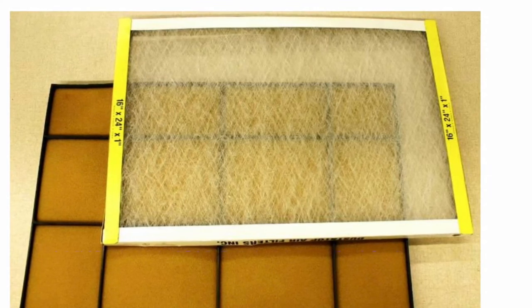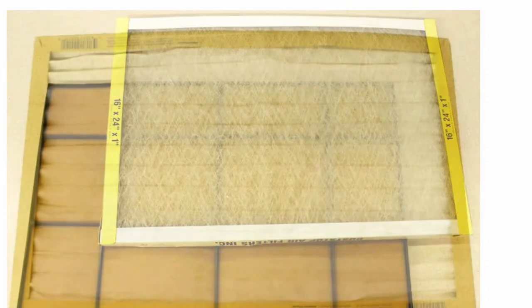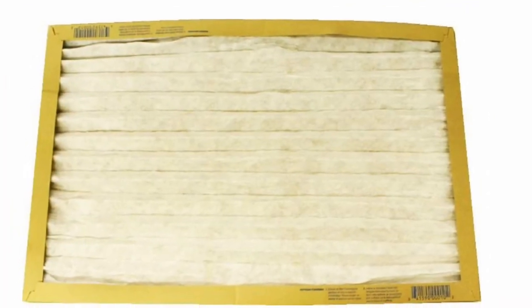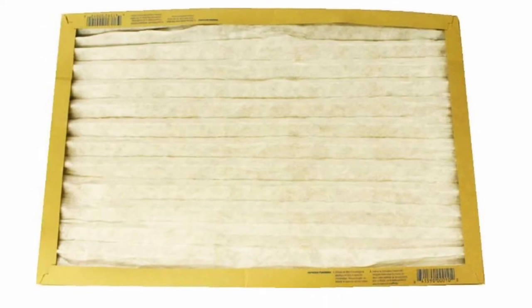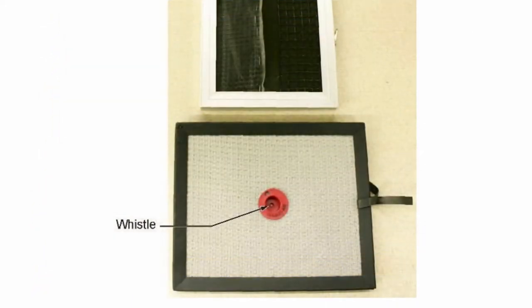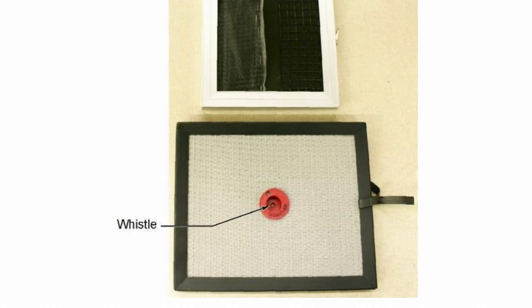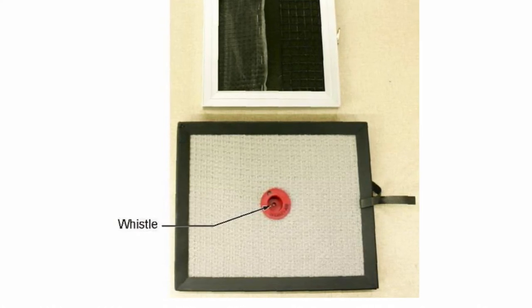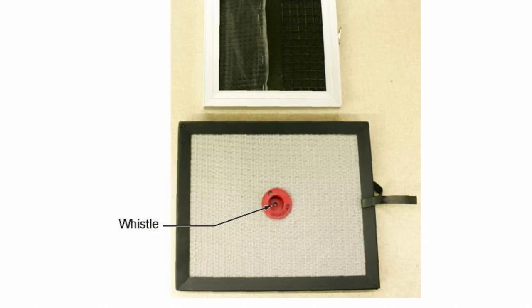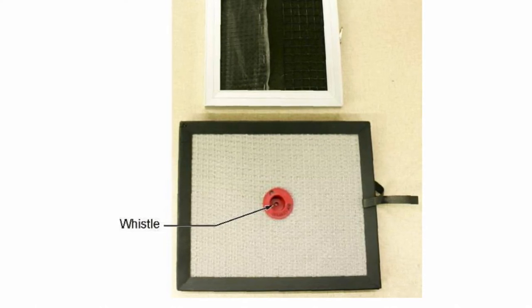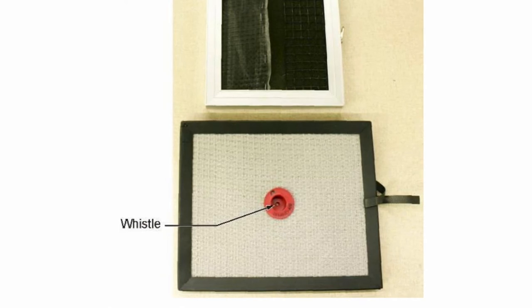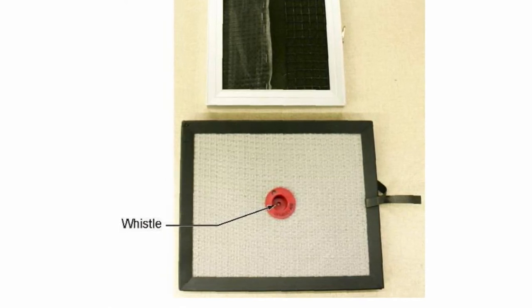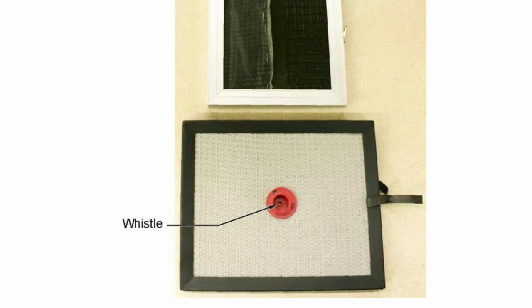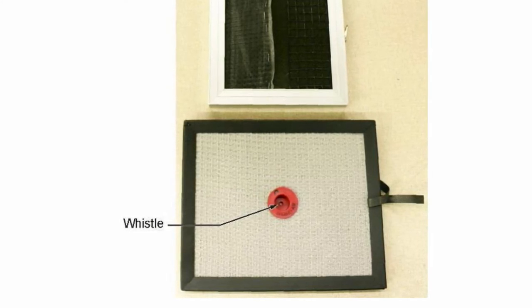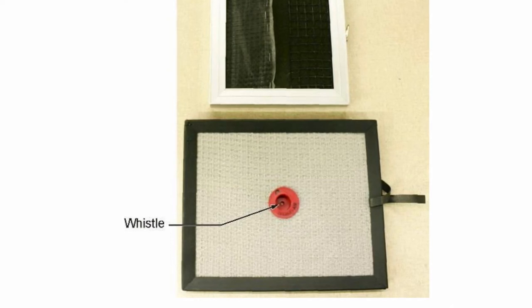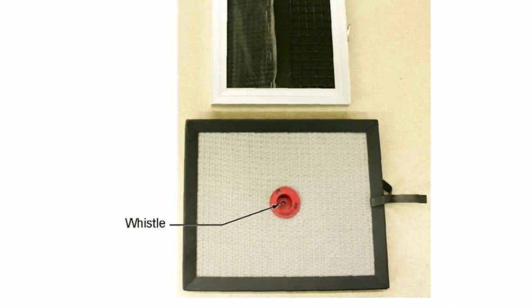This filter is a disposable fibrous media filter in a cardboard frame. This one here is a pleated filter, disposable in a cardboard frame. This one right here is an electrostatic filter. When air passes over this type of filter, it becomes statically charged, which then will attract some of the particles inside that same air. The static charge of these filters is better in dry periods and will become less efficient during humid seasons.